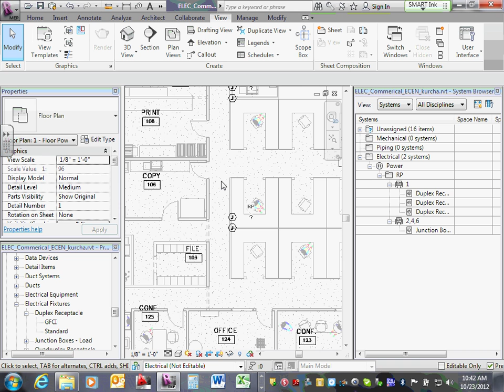So the rest of the receptacles are done the same way. The only thing you need to pay attention to is no more than 6 duplicate receptacles on 1 circuit, and make sure the quad receptacles are on a separate circuit than the non-quad, because the quad receptacles are meant to be data receptacles - they're circuited separately. So for the quad, grab 2 quads and put them in 1 circuit, giving you 4 receptacles. For the other duplicates, grab 6 of them in 1 circuit and move on. Start from north to south and keep going.